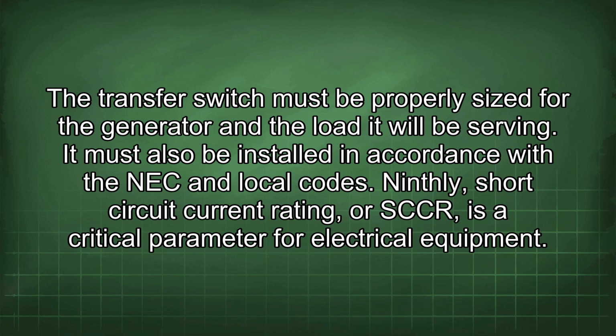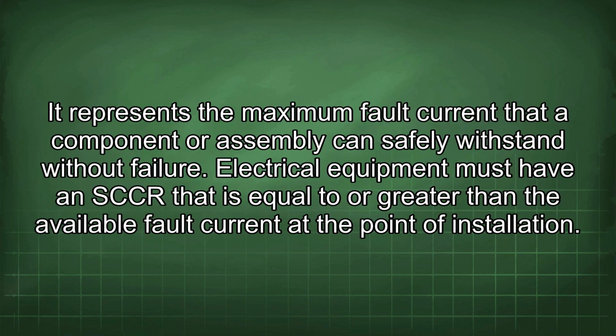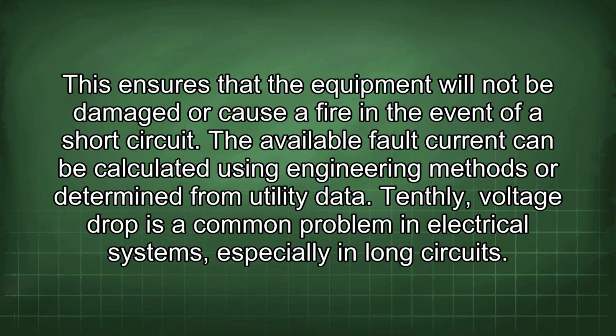Ninthly, short circuit current rating, or SCCR, is a critical parameter for electrical equipment. It represents the maximum fault current that a component or assembly can safely withstand without failure. Electrical equipment must have an SCCR that is equal to or greater than the available fault current at the point of installation. This ensures that the equipment will not be damaged or cause a fire in the event of a short circuit. The available fault current can be calculated using engineering methods or determined from utility data.